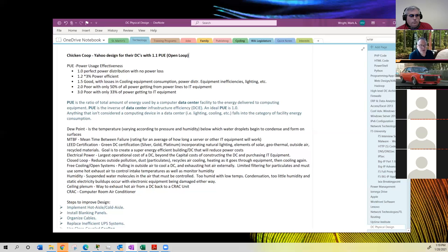An open loop is a lot more variable. You've got cold air coming in, but at different degrees based on the outside ambient temperature, and different humidity levels - it can be more or less humid depending on the weather in that area. If there's a forest fire, you're going to suck smoke right into your data center. If it's a dust storm, there's some filtering, but that dust is probably going to come in too. So with an open loop you've got a lot of variables.